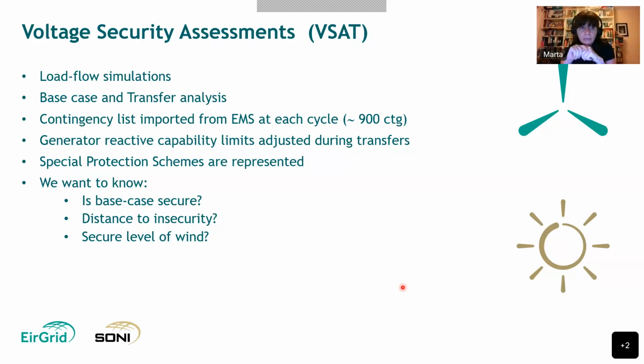VSAT also takes into account the reactive capability curves of each generator. So when we're scaling wind or conventional generation up and down, the reactive capabilities, the limits, are adjusted accordingly. Any protection schemes are also represented and captured in the simulations.